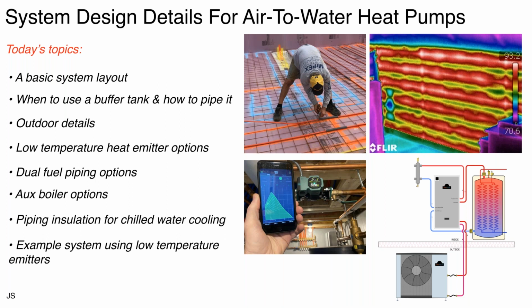One of the critical design concepts with any heat pump, be it an air to water heat pump or, let's say, a geothermal water to water heat pump going to a hydronic system, is to keep those supply water temperatures as low as practical. The lower we can keep those temperatures, the higher the coefficient of performance on that unit is going to be. We're also going to look at dual fuel options, and by that we mean, for example, in a retrofit, there may already be a boiler present in the system, and when we add the heat pump, how do we tie that boiler in? Or in a new construction application, if somebody wants a backup, there are different ways to pipe that in. We're going to show you some different options on that. We're also going to look at a bit of chilled water piping details.